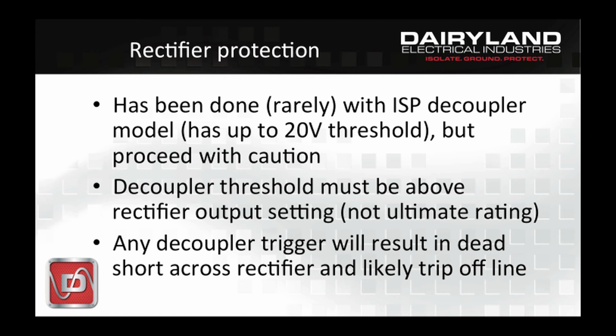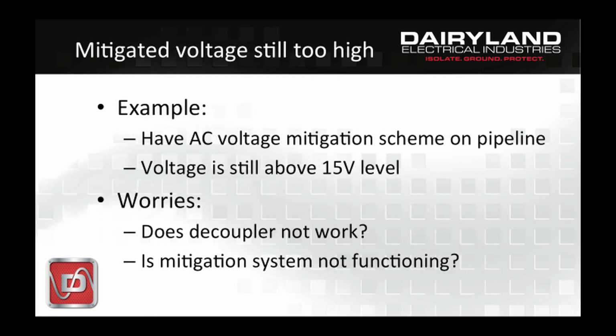but it is not recommended because the operation of any decoupler is still, upon reaching the threshold voltage, say during a fault or lightning condition or any electrical disturbance, the decoupler will still trigger into the shorted mode and it's going to cause a short across the output of the rectifier, and it's going to still trip the rectifier offline. Some clients have said, well, we can live with that, but we do caution against doing this. This is the one exception to the previous discussion.